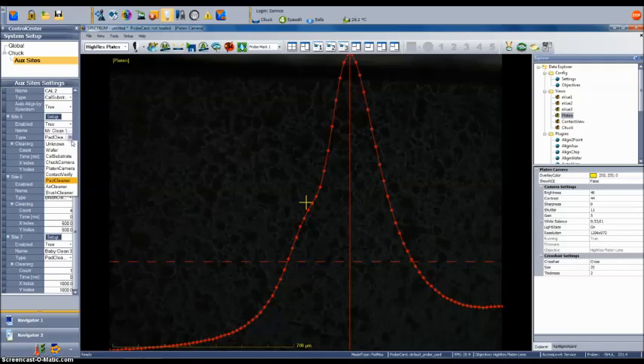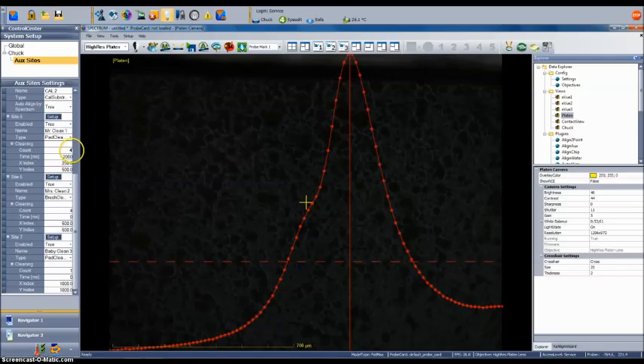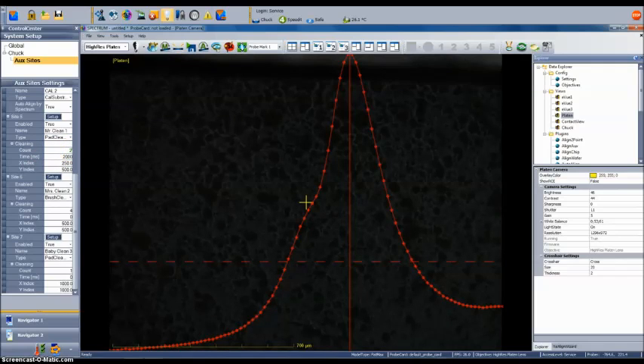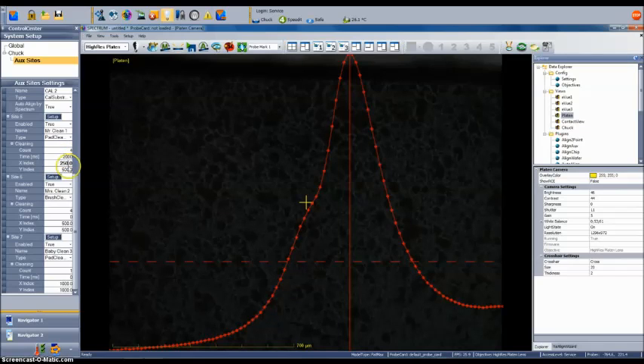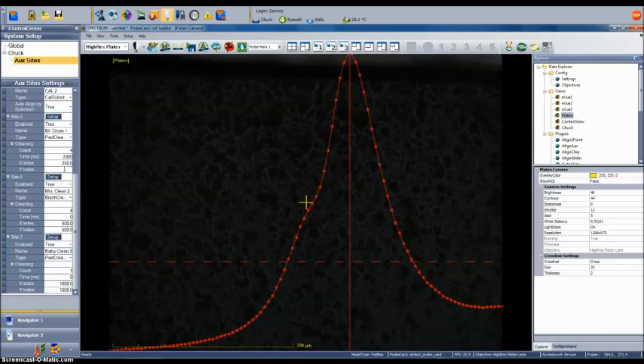There are also cleaning recipe parameters. You can set the number of times the chuck will be raised into the cleaning medium when an operation is called. You can set the length of time the chuck is raised into contact with the tips per stroke. And then finally you can set the x and y index value to be the distance traveled in x and y between each clean pad contact event.